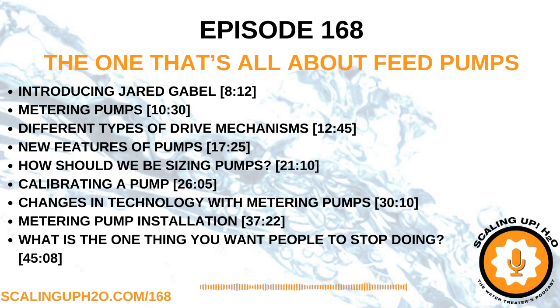But if you don't know that, there's also some great guidance out there in the Cole Parmer world. There's a Cole Parmer website with a compatibility chart that gives you some guidance. And we always use the word guidance because it's hard to know whether the chemical being used is a proprietary chemical with some blend that we don't really know about, or something more standard in the water treatment world, like bisulfites or hydrochloric acids, peracetic acids, things like that. So we can use the chemical compatibility charts that exist online or in other areas. We do provide guidance. A lot of the manufacturers of pumps will provide a guidance sheet for that.